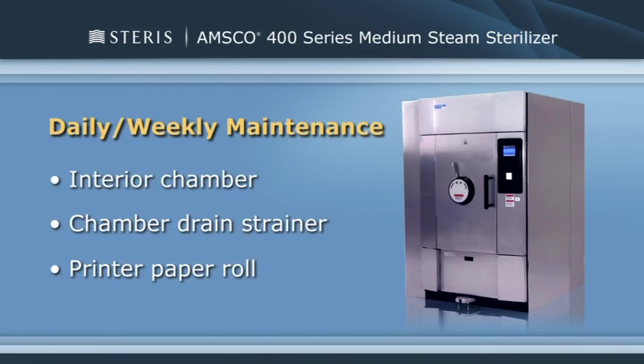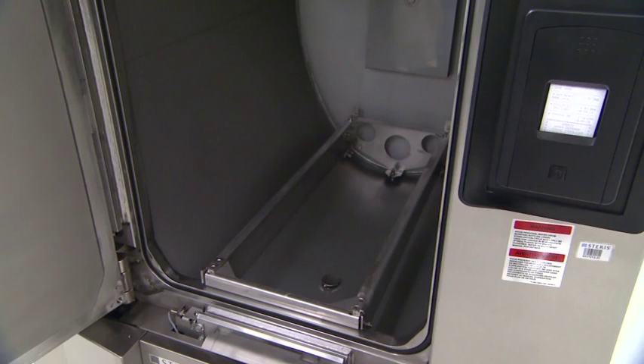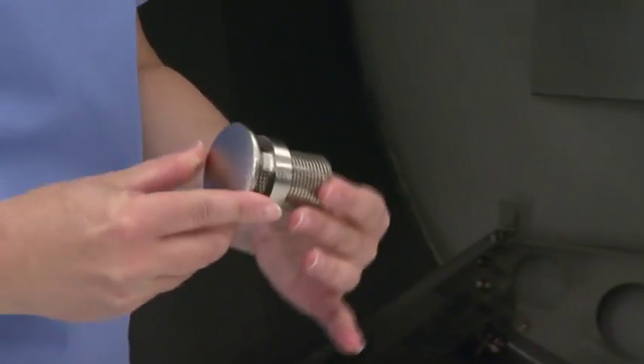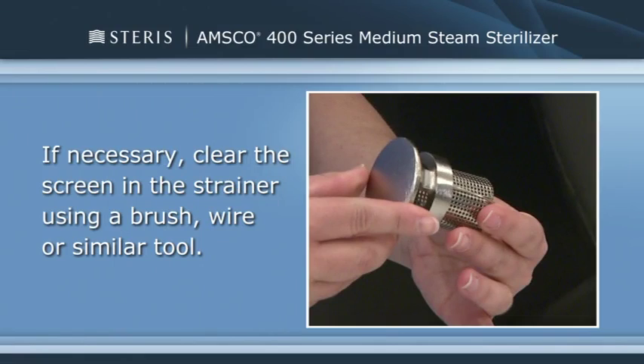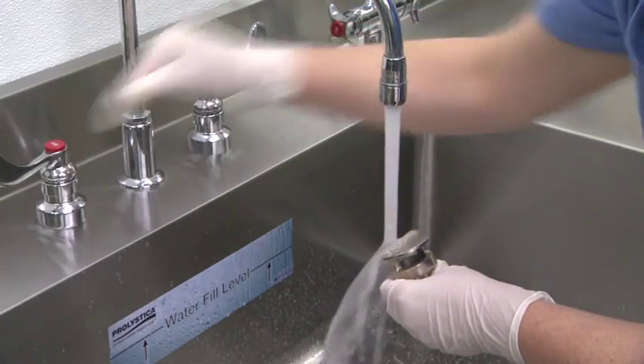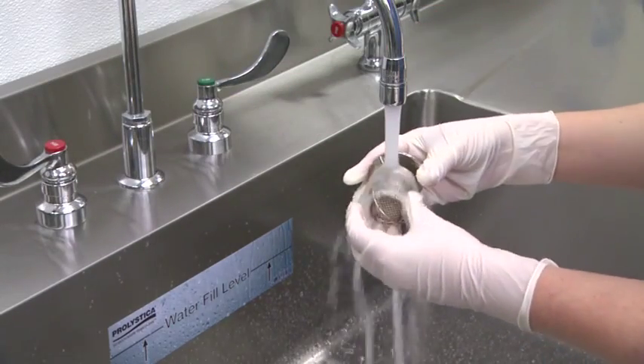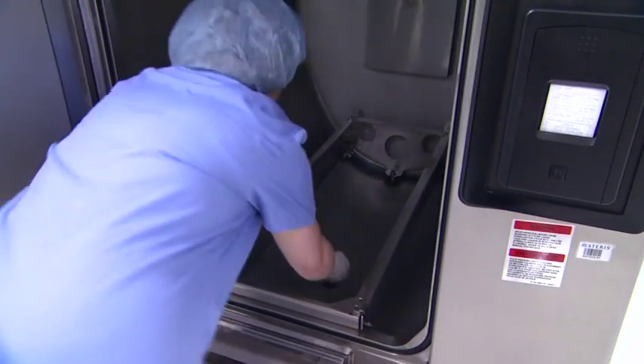STERIS recommends inspecting the interior chamber and chamber drain strainer each morning before running the daily warm-up cycle. Start by cleaning the chamber drain strainer, preferably after the final cycle of the day has been run. Remove it from the drain in the bottom of the chamber. Remove any obvious debris and, if necessary, clear the screen in the strainer using a brush, wire, or similar tool. Once it has been cleared of obvious debris, reverse flush the strainer under running water. Replace the strainer in the chamber drain.